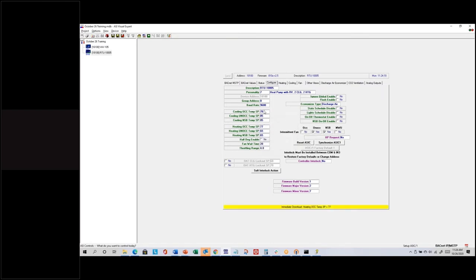To get this to ramp more quickly, I can raise my set points. On the configure tab, I'll change the heating set point to 77 and the cooling setpoint to 79. The nature of the PI calculation is that the further away you get from set point, the faster it should ramp toward 100 percent.